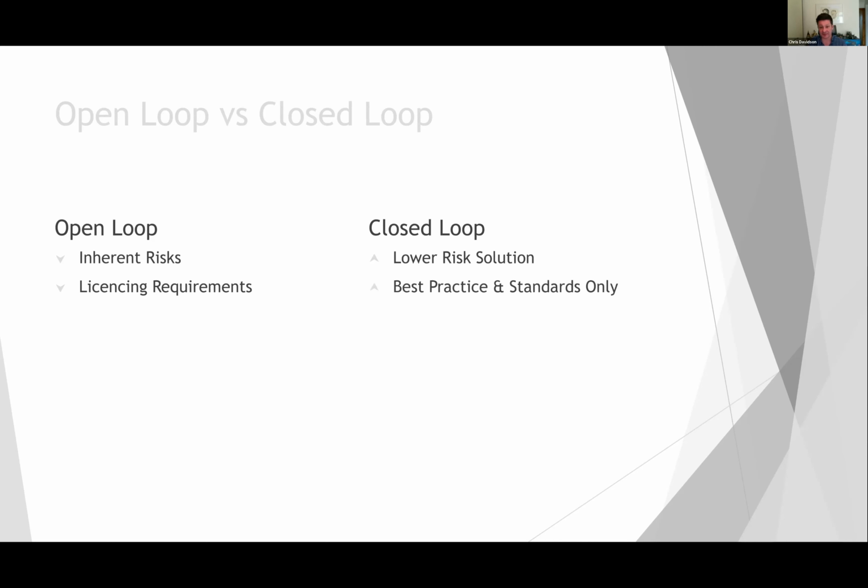On the upside, from a closed loop point of view, there are no licensing requirements. However, there are best practices and standards that we need to work to. The best standards that are applicable to the systems are maintained by the Ground Source Heat Pump Association, particularly the vertical borehole standards and the environmental standards, which were written originally by the Environment Agency, but are now maintained by the Ground Source Heat Pump Association. So we're dealing with a lesser level of regulation for closed loop than we are with open loop.